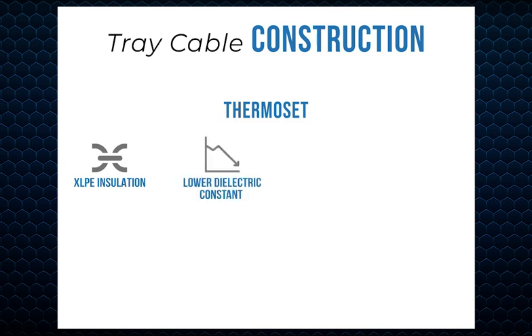XHHW-2 is a thermoset product. Cross-linked products like XHHW have XLPE insulation instead of PVC, which is more resistant to chemicals, ozone, and abrasions. XLPE has a lower dielectric constant than PVC for better performance. Because of the modern chemistries involved, modern XLPE is far less toxic than PVC in the event of fire. Additionally, thermosets offer improved physical and electrical properties and are more flexible at lower temperatures.